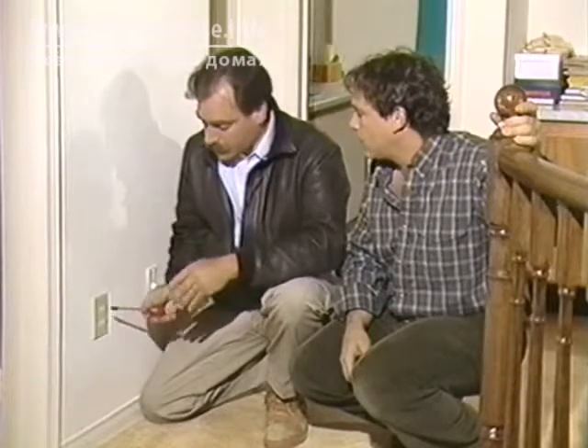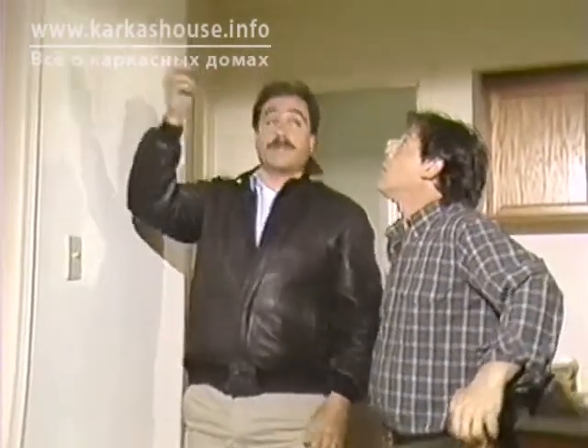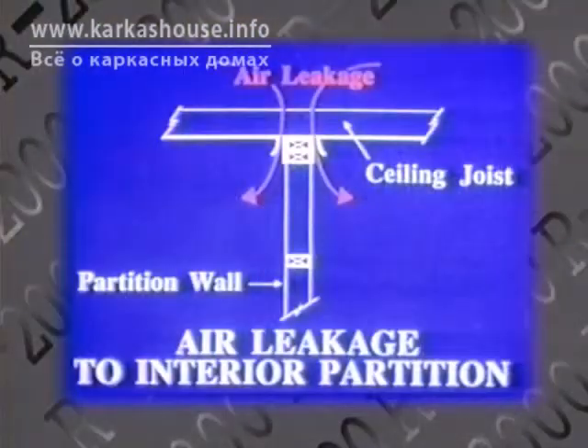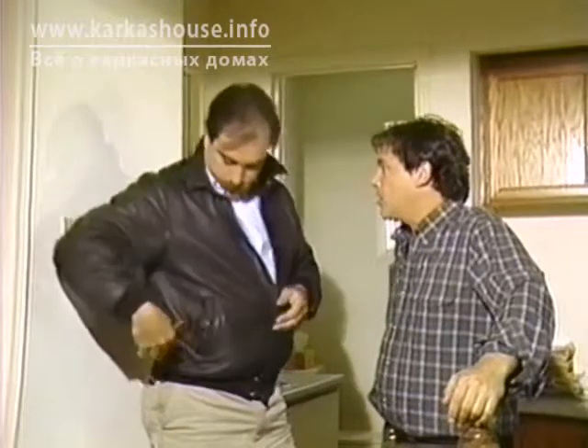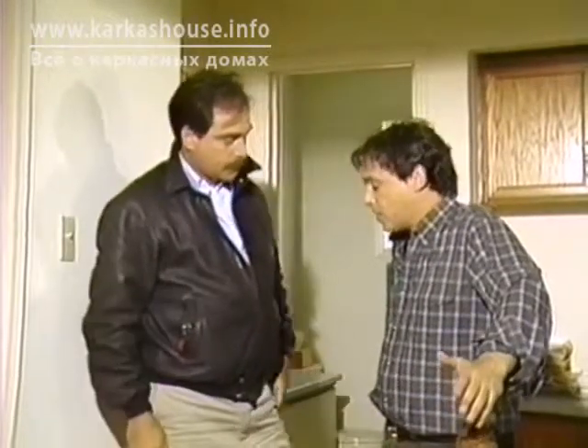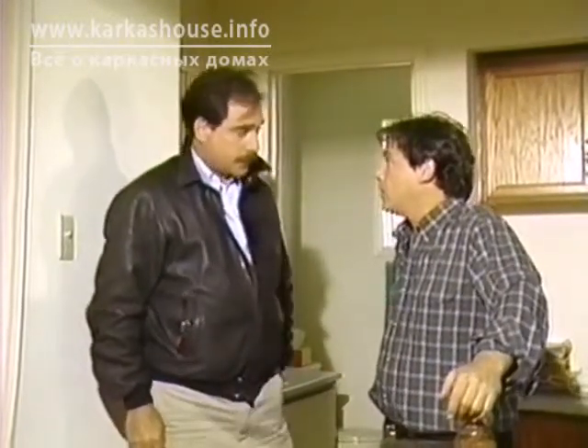Well, it's because of the way in which the electrician ran the electrical wires when he wired the house. The thing to remember is that above us is attic space. It's really outside the building. And whenever there are holes left through top plates in the wall, those are going to leak as badly as any other leaks in the building. This is all pretty typical for conventional construction, I understand. It's obviously a problem, right? No, it certainly is. It's a very serious problem.